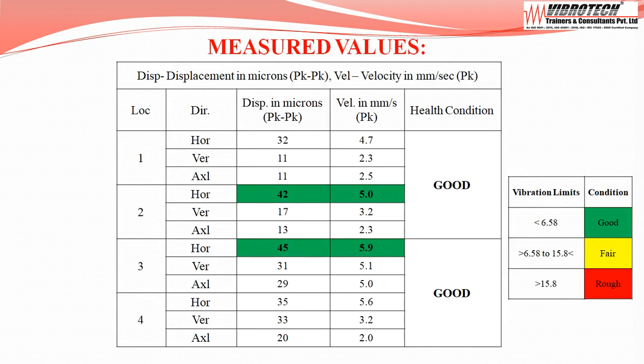Vibration data are collected. The maximum values are at motor drive end horizontal — velocity up to 5.0 mm per second peak with displacement of 42 microns peak to peak — and at pump drive end horizontal, velocity up to 5.9 mm per second peak with displacement of 45 microns peak to peak. The equipment health condition is good.